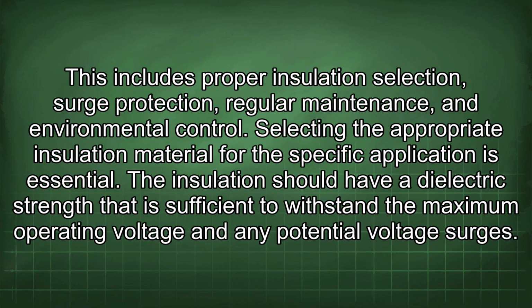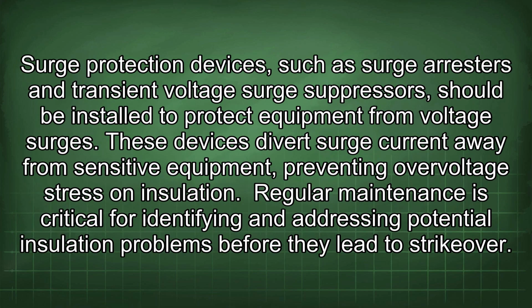This includes proper insulation selection, surge protection, regular maintenance, and environmental control. Selecting the appropriate insulation material for the specific application is essential. The insulation should have a dielectric strength that is sufficient to withstand the maximum operating voltage and any potential voltage surges. Surge protection devices, such as surge arresters and transient voltage surge suppressors, should be installed to protect equipment from voltage surges. These devices divert surge current away from sensitive equipment, preventing overvoltage stress on insulation.